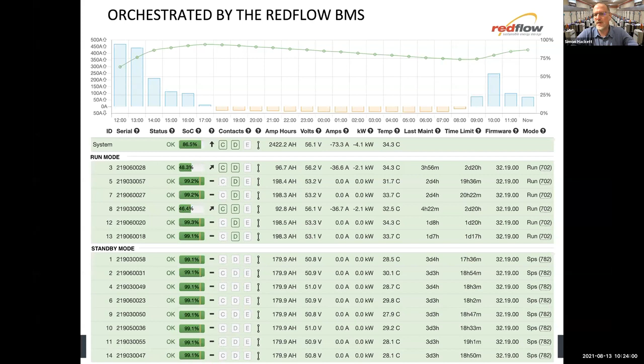Last thing I want to talk about is a thing we call PodZ, Z for zinc, since these things use zinc inside them. One of the things we've done in the last several months is design a modular way to start bringing our batteries up to grid scale, similar to what you see with lithium container deployments. That picture is the first instantiation of what we've built this way. We can build various sizes, but this has been a good starting size. Each of the gray cubes has 16 of our batteries in it, 10 kilowatt hours each, so that's 160 kilowatt hours per box.